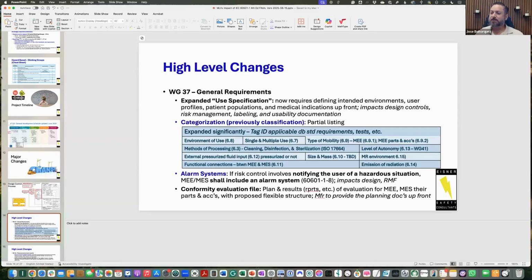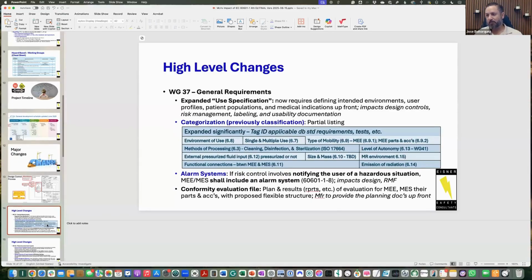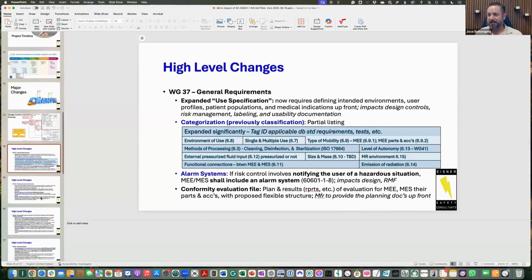Yeah, Leo, just curious, given that you're incorporating so many different topics, like the software requirement specifications I saw on the previous page, how aligned is that going to be with 62304? Or with the cybersecurity, how aligned is that going to be with SW96? Because one of the big challenges you end up facing is, if you're having to follow multiple standards for the same documentation or the same process, it just becomes very confusing and conflicting. So I'm just curious what that's looking like.